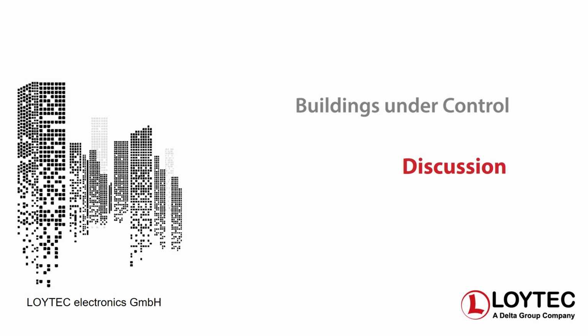Yeah, actually, maybe two comments that were not in this presentation. Typically, you use historic filters when you have a counter. You have an energy counter that is just continuously counting up, and somewhere you want to display the power consumption over the last 15 minutes, the last day, the last week, the last month, whatever.